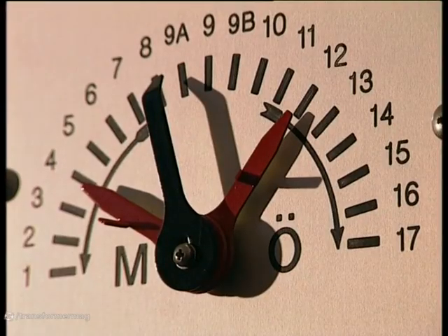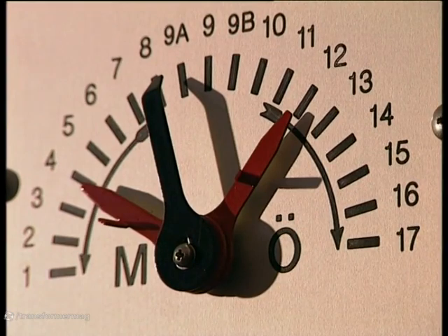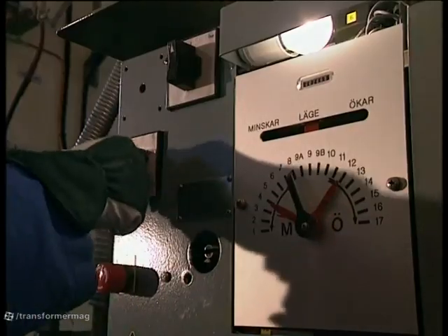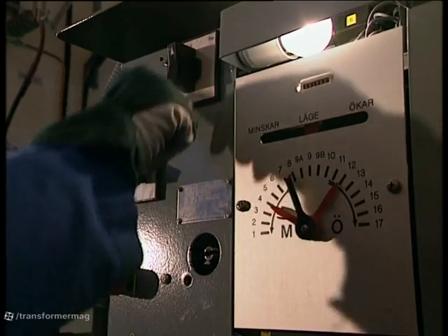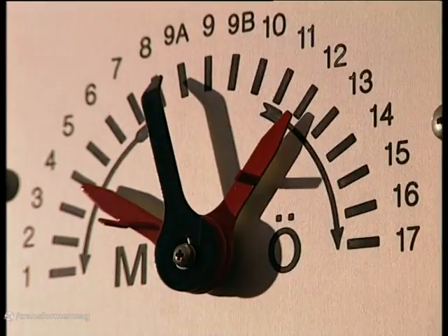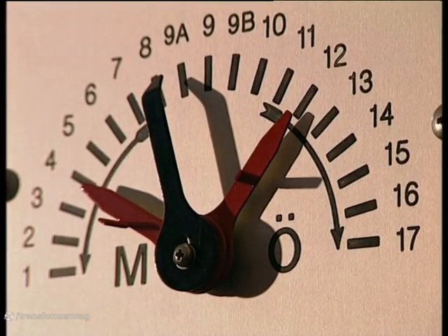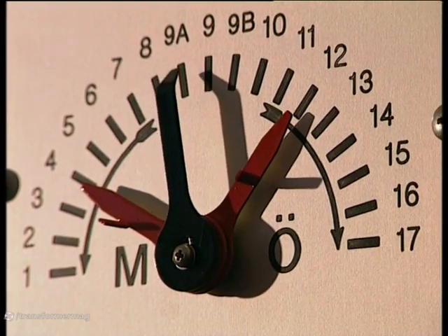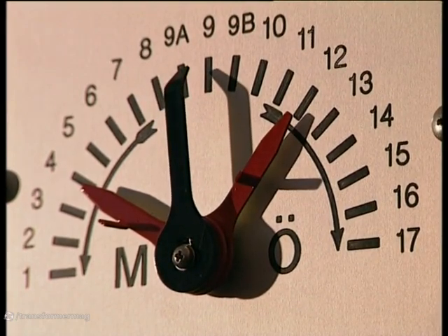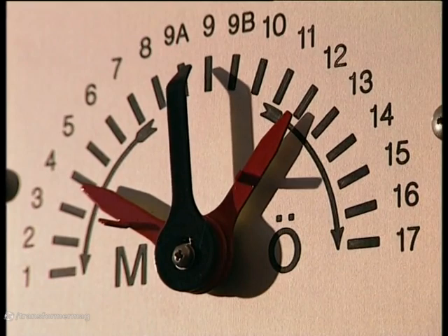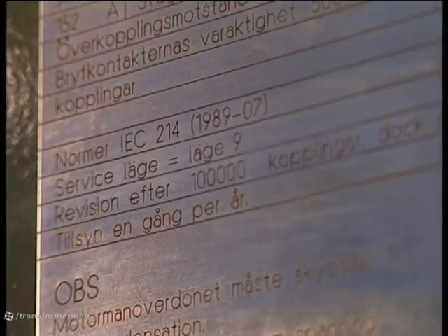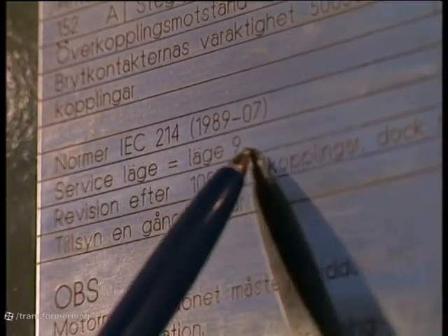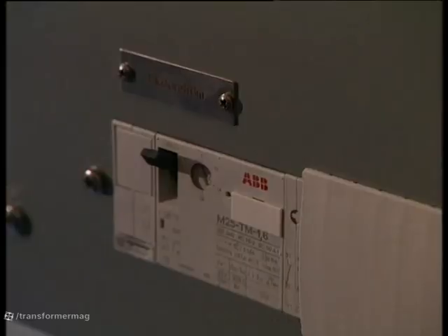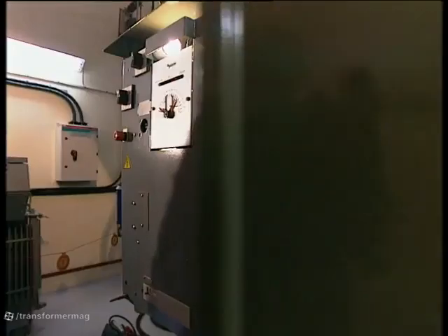Before starting work, note the position of the motor drive mechanism. Set the tap changer to the service position as indicated by the plate on the door of the motor drive mechanism and open the motor circuit breaker.